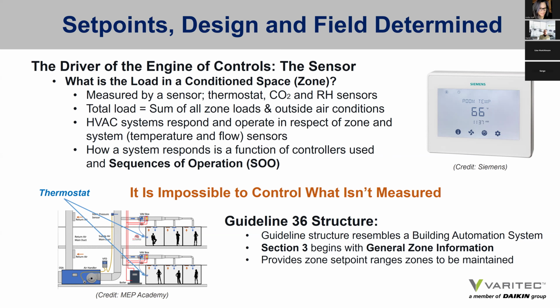The sensor actually measures the amount of thermal energy in the space, or the volume of airflow rate actually being supplied to a space. And the total load read by the thermostat and other sensors, such as relative humidity sensors and perhaps even CO2 sensors, is the sum of all zone loads in the space, as well as the actual load inherent in the outdoor condition.